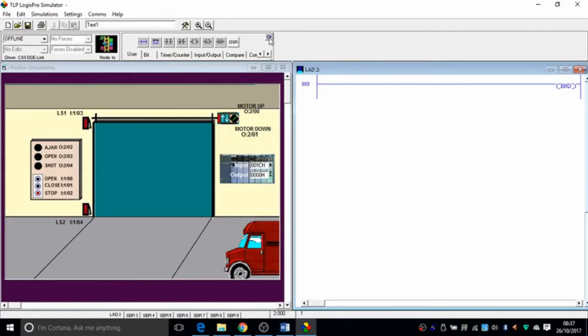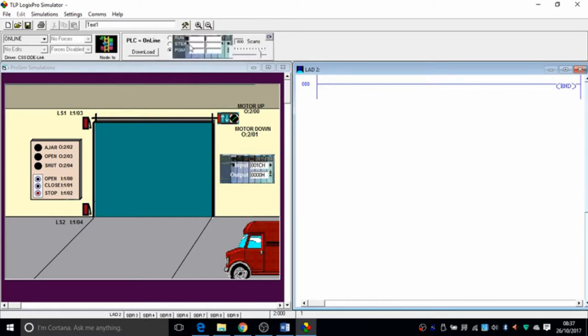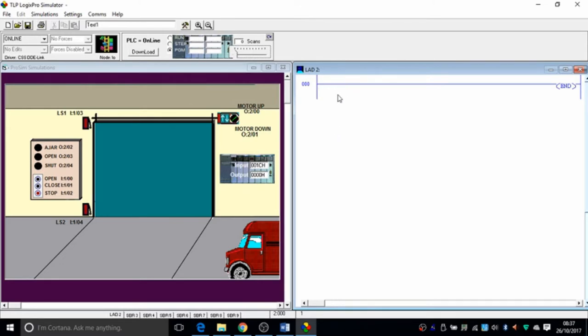The way you do it, you press this to show up your PLC control panel. When you're programming, you put this on program mode; when you're running it, you put it on run mode, and you have to download before you run it. This one is the scan speed — the speed of the scanning of the program — so if you bring it right down to minimum, once it's run you can see how the contacts are operating and the coils are coming in and out of the circuit.